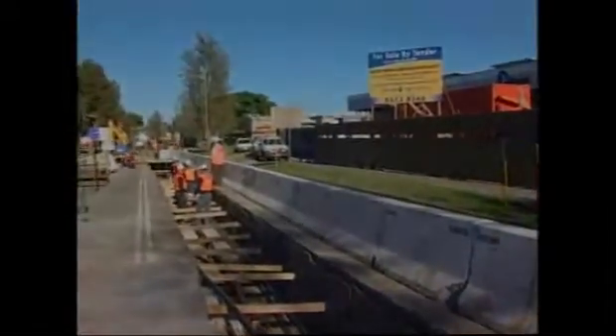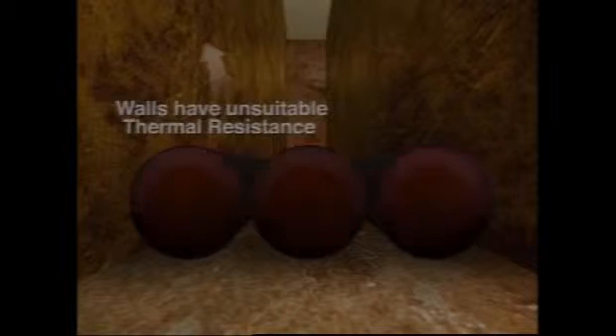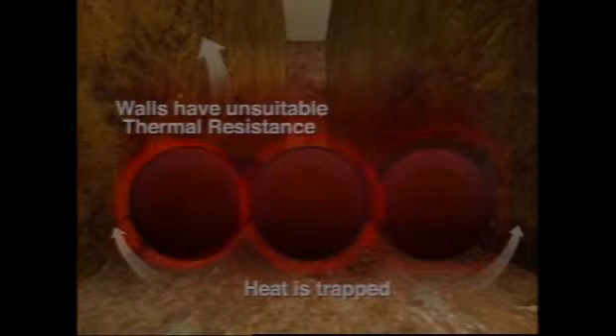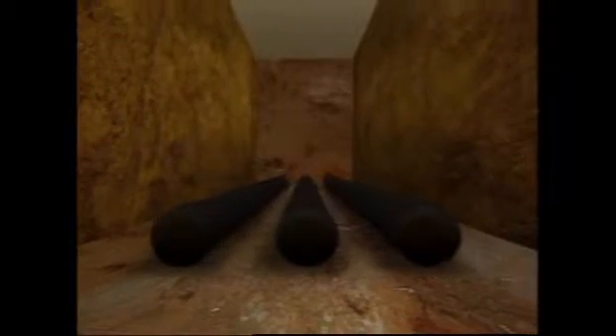The issues are simple enough. Electricity flowing through a conductor generates heat. Any resistance to that heat in the surrounding environment causes the cable to overheat. So this trapping of the heat has to be avoided or minimized. This could mean cable and trenches, or both, have to be larger, or the space between circuits made much wider.